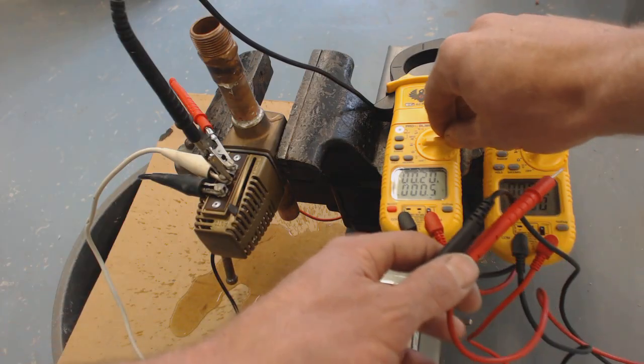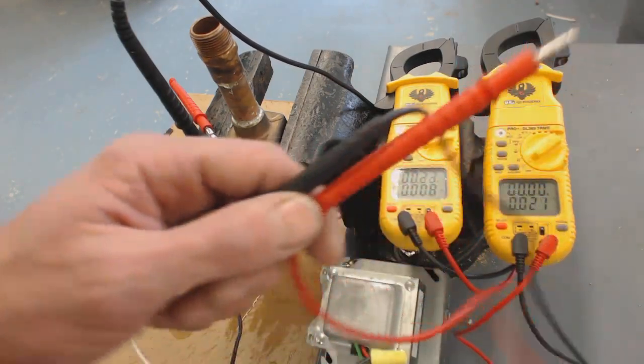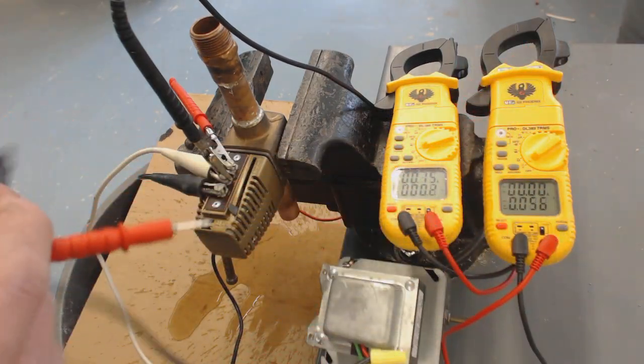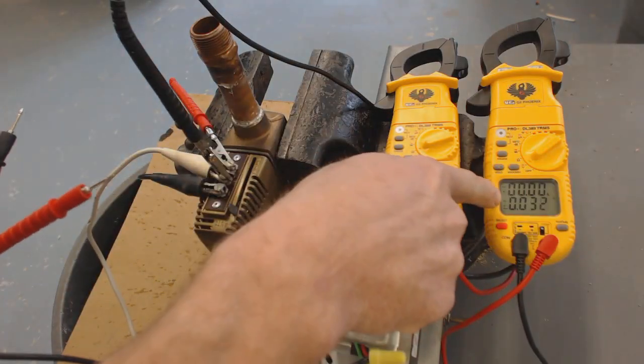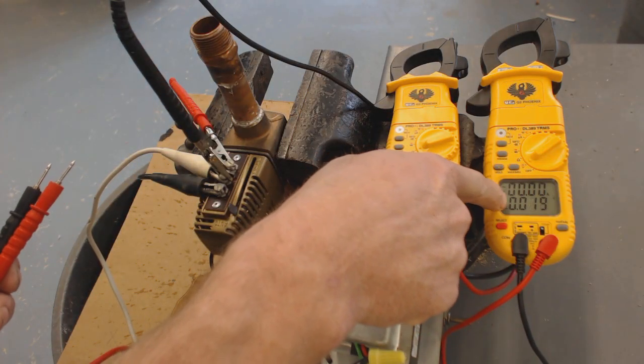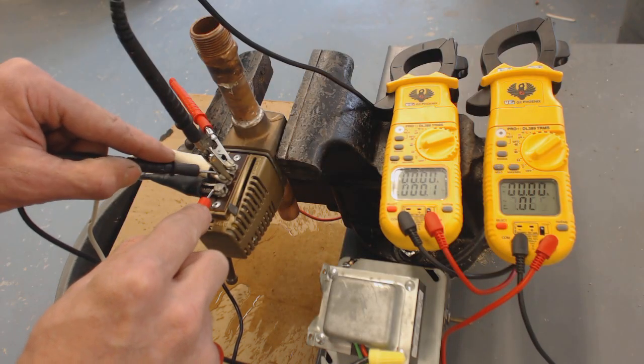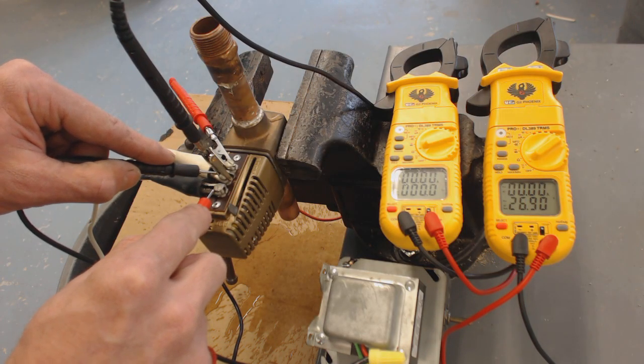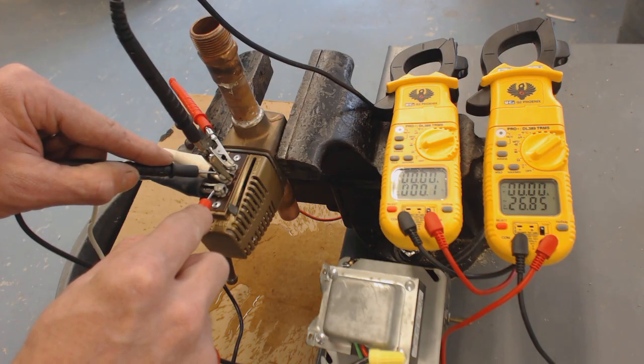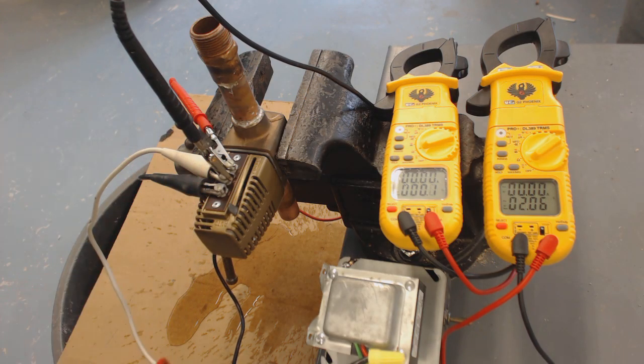I'm just going to turn this down to resistance. So we'll see the 0.0, but it won't make the noise. Now with this multimeter we can check for voltage right now from screw 1 to screw 2. And that one says 26.85. Anything higher than 24 volts is good. So that's how it works.